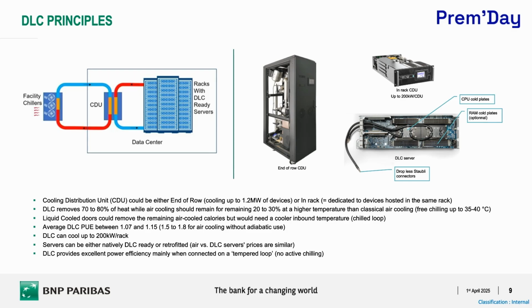And each CDU is then delivering the cold water and the cold liquid to the servers that are racked in the rack. So the end-of-row CDUs can reach 1.2 megawatt each. We usually put 2 of them to have redundancy, but all those systems have an inner redundancy. They have 2 pumps, they have 2 of everything. Everything is doubled. So it's a pure decision for BNP Paribas to put 2 of them, because if we lose 1 CDU, we lose the whole cage. And if we lose the whole cage, it will cost much more than a CDU. So we decided to put 2 of them.